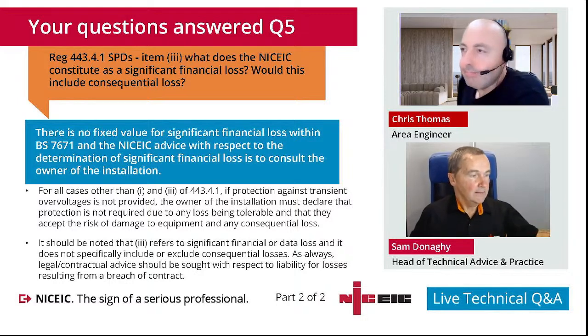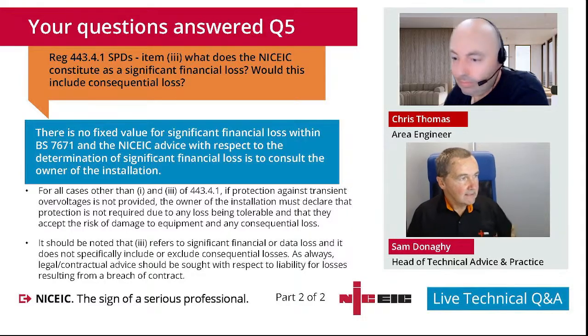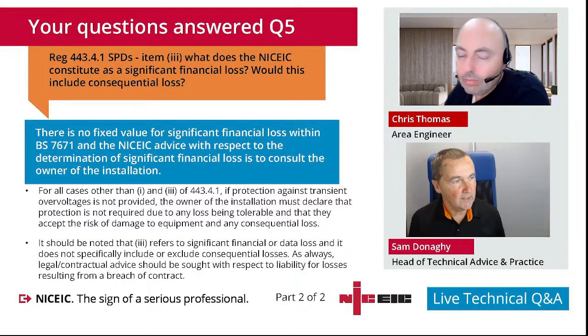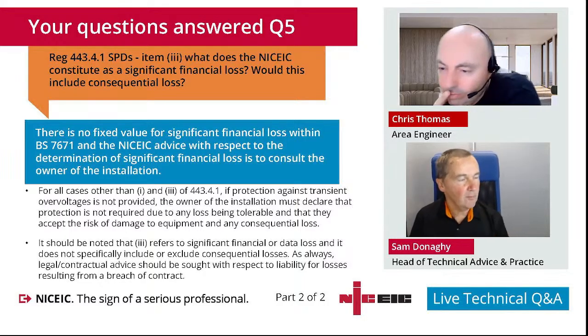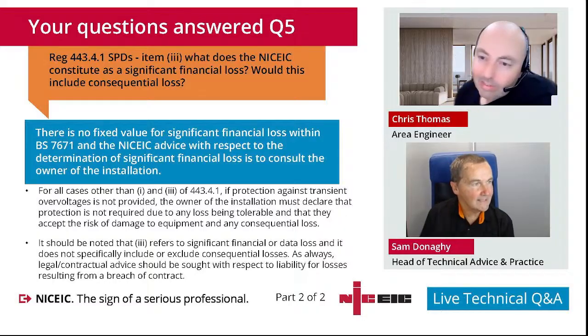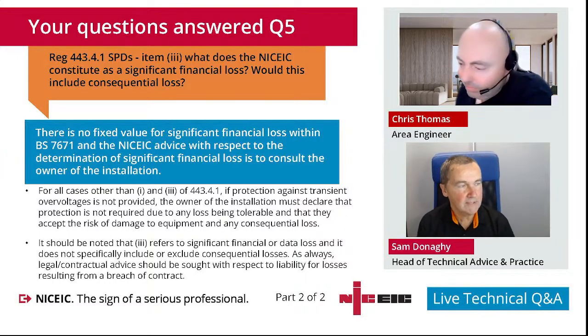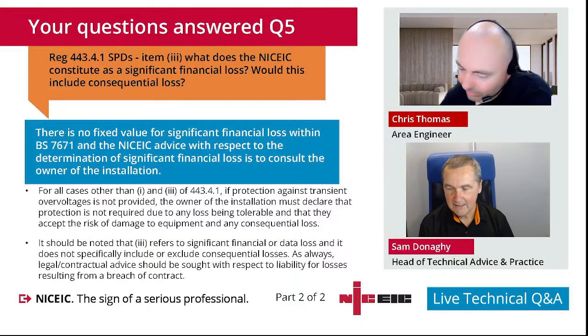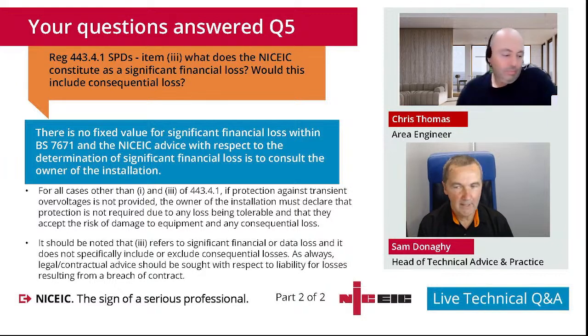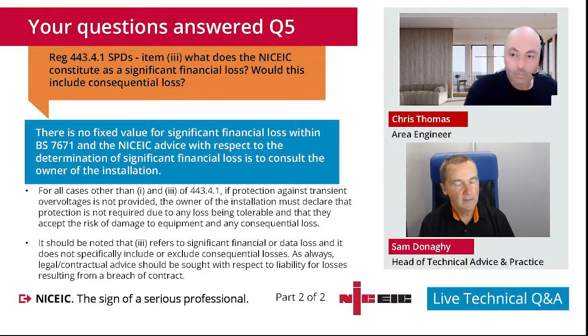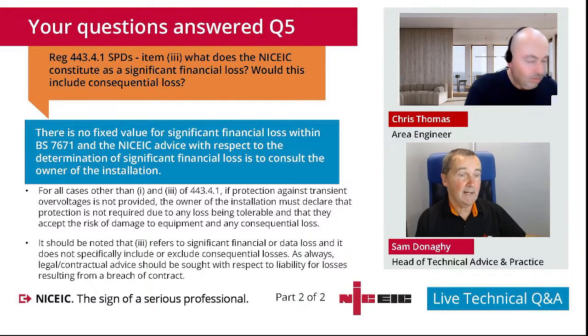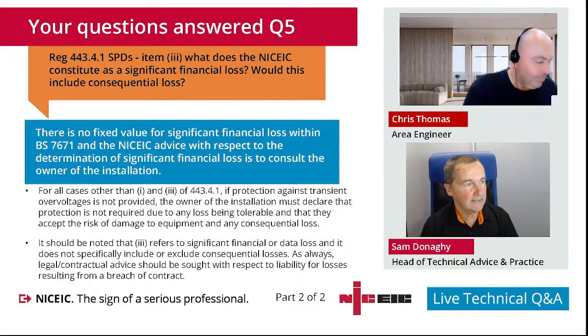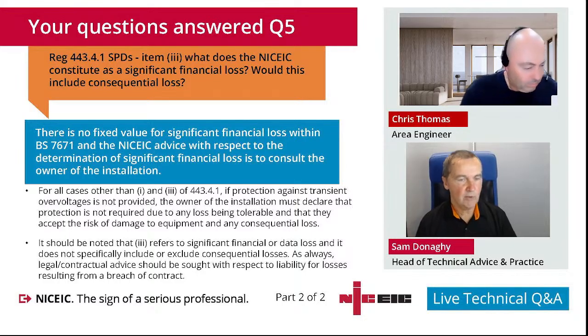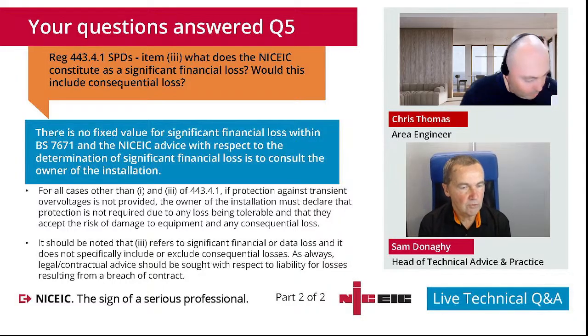Absolutely. Another one that came in earlier is, again, a little bit similar to the question that we talked about with regards to the 16 amp on a 16 mil cable on a 100 amp supply. We've now got the other way round. We've got a 6 mil ring circuit on a 40 amp RCBO. Is that fine? So from a current carrying capacity, it would be fine, because although 6 mil cable, we haven't got the information of how it's installed, whether it's clip direct or what, but if we take clip direct, then 6 mil would generally carry more than 40 amps, so there's nothing to stop it, and it wouldn't cause any issues with overload.